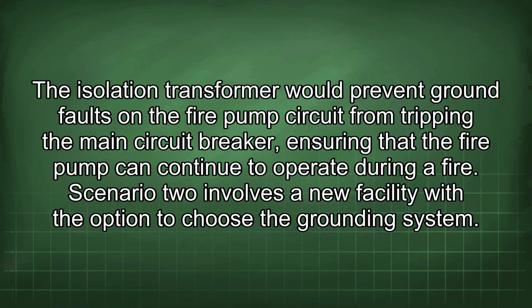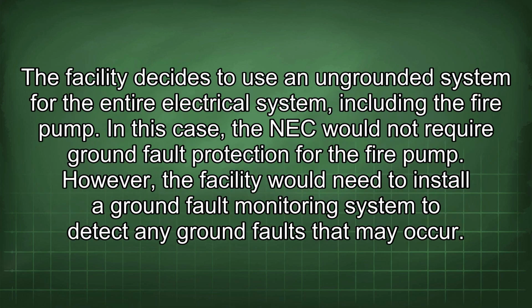Scenario 2 involves a new facility with the option to choose the grounding system. The facility decides to use an ungrounded system for the entire electrical system, including the fire pump. In this case, the NEC would not require ground fault protection for the fire pump. However, the facility would need to install a ground fault monitoring system to detect any ground faults that may occur.